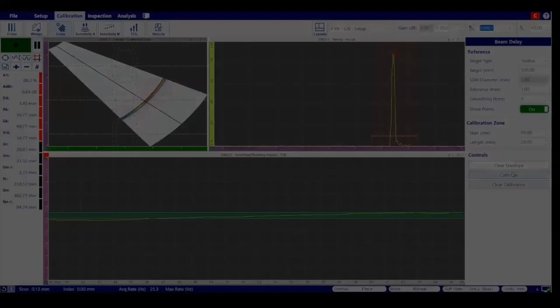Coming to the sensitivity calibration, we can do either a manual calibration or an automatic calibration. Manual means we take individual side drill holes and get the envelope for all the elements. We can see the points at which every angle has been captured.